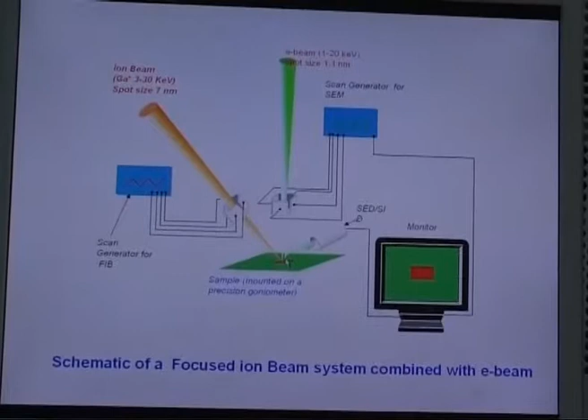As you see here, there are some electrostatic arrangements, two parallel plates in coupling. Here also you can see two parallel plates opposite to each other, and these are all for generating scan images of the patterns you want to generate. We can generate any bitmap image and make the ion beam go in that fashion, so that you can image the patterns made by FIB. The purpose of the dual beam is that whatever you structure with the ion beam, you can simultaneously image by electron beam or later on. You do not have to take out your sample. So that's the usefulness of having a dual beam.